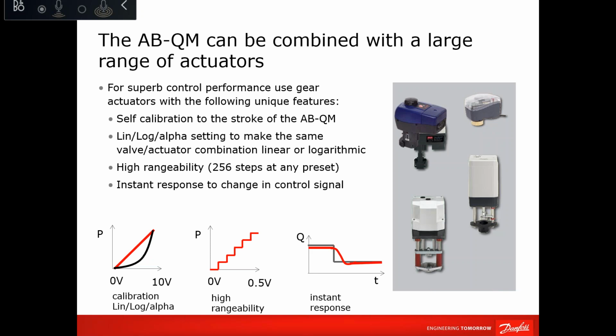If we take the lin-log alpha, which means you can select what will be the characteristic on your control part of the valve. In our case, both are available because this PIBCV can be used in application where water to water exchange or in application where water to air exchange. And that is very important to have in a single valve, because if you don't, then you need a complete model of valve for AHUs, FCUs, and another model for chilled beams, radiator, heat exchange. In our case, you can achieve both by using the combination of the valve and actuator.